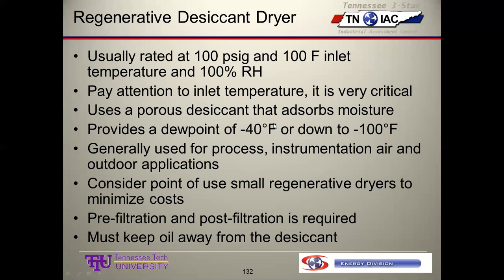It uses a porous desiccant. So this is adsorption, A-D-S-O-R-P-T-I-O-N, which adsorbs moisture, which means the water vapor molecules just kind of stick to it. It has lots of cracks and crevices, and it has a low vapor pressure. The moisture in the air has a high vapor pressure, so it basically sticks to it until it becomes saturated, and then all of the sites that a molecule could stick to are occupied, and it can't adsorb anymore. So then we have to regen it, or drive that moisture out. And we'll talk more about that in just a second.